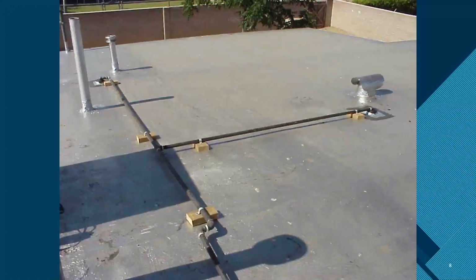Pretty cool. Okay, here we are on a built-up painted roof. They've replumbed it, and I can see the sewer vent right here sticking up. Here's a vent for probably a water heater in the background with a cap. What's the support requirement for gas lines? How often? Every 8 feet for 3/4 inch. Every 8 feet. Just say that, and then you're fine. So every 8 feet and every joint.